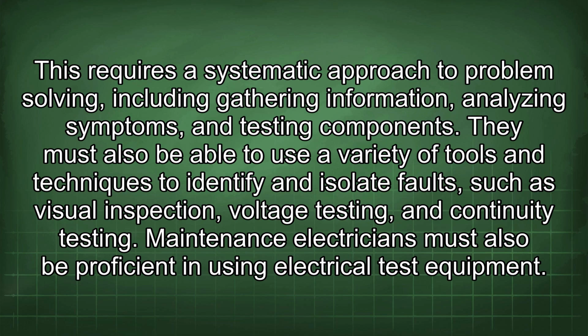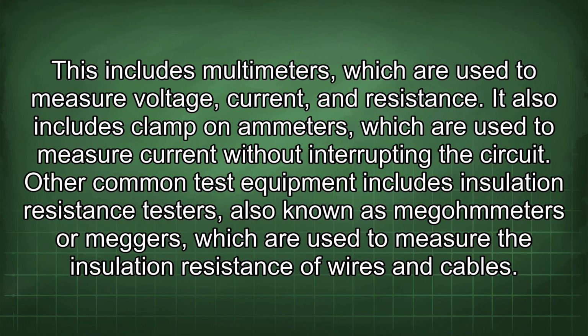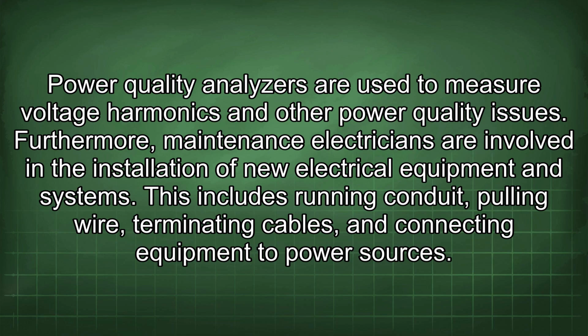Maintenance electricians must also be proficient in using electrical test equipment. This includes multimeters, which are used to measure voltage, current, and resistance. It also includes clamp-on ammeters, which are used to measure current without interrupting the circuit. Other common test equipment includes insulation resistance testers, also known as megohmmeters or meggers, which are used to measure the insulation resistance of wires and cables. Power quality analyzers are used to measure voltage harmonics and other power quality issues.